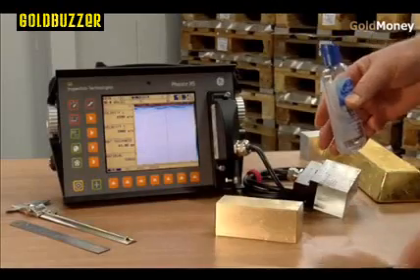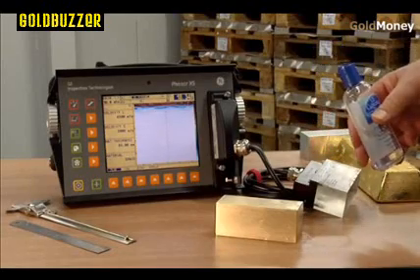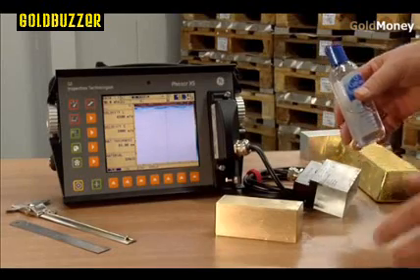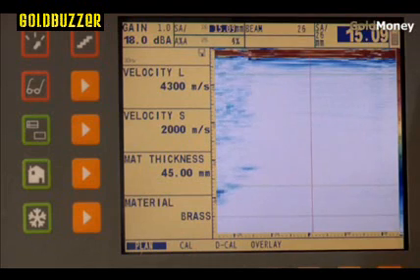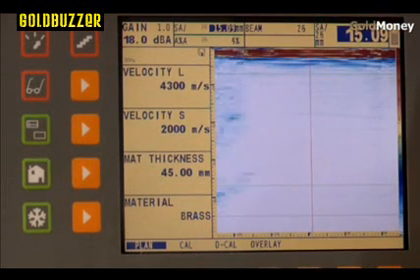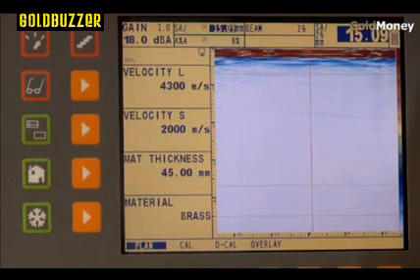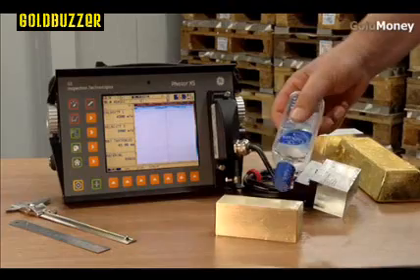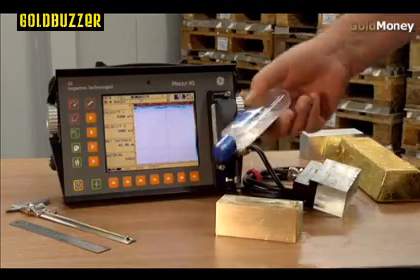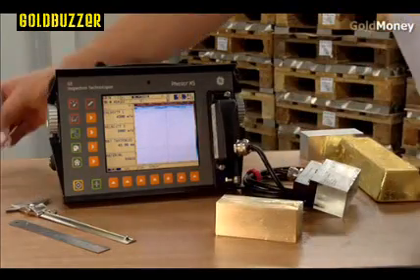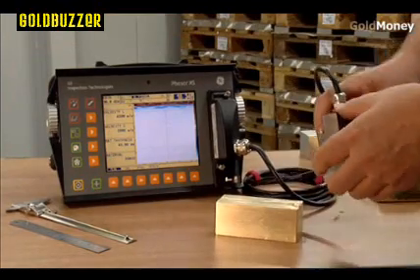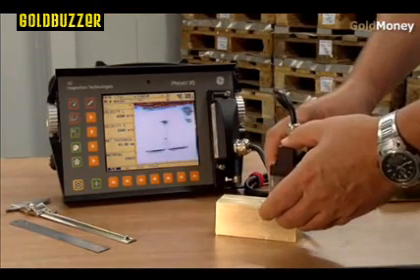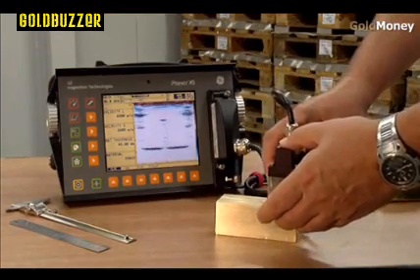We're now going to test a brass sample with the phased array. The first thing we have to do is select a different material for the instrument, which changes the acoustic velocity. We then need to put the couplant on in exactly the same way that we did with the gold bar. Now we put the probe on and we have our section.